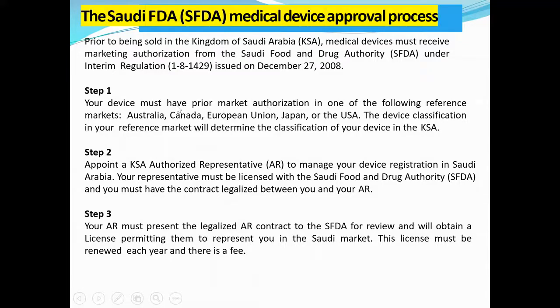If your device has prior market authorization from Australia, Canada, Europe, Japan, or USA, the device classification in your reference market will determine the classification of your device in the KSA. Then appoint a KSA authorized representative, that is AR, to manage your device registration in Saudi Arabia. AR is nothing but your local agent. Your representative must be licensed with the SFDA and you must have the contract legalized between you and your AR. Your AR must present the legalized AR contract to the SFDA for review and will obtain a license permitting them to represent you in the Saudi market.